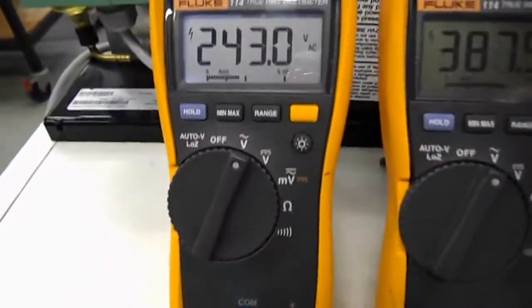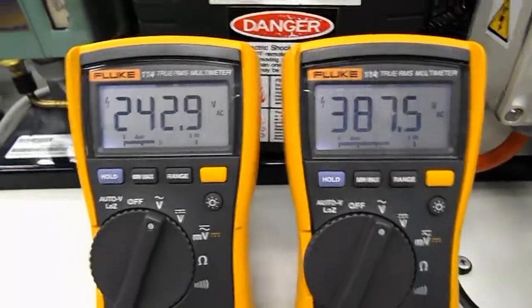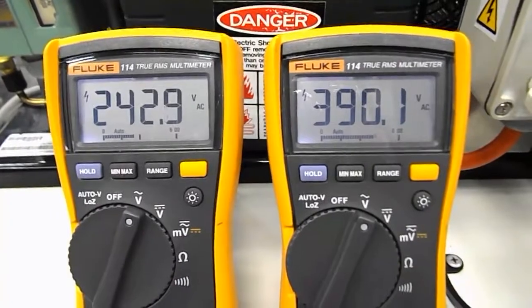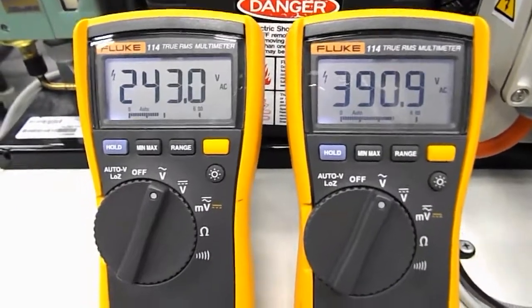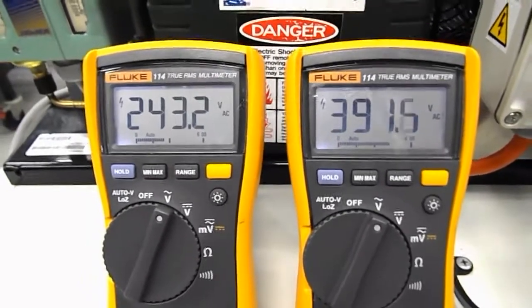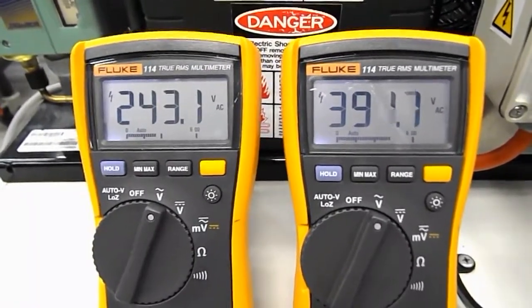As you can see, the left-hand side is showing you the primary source voltage and the right-hand side is showing you the back EMF which is being produced well and truly after 75% RPM from the motor — and in some cases these can exceed 400 volts.